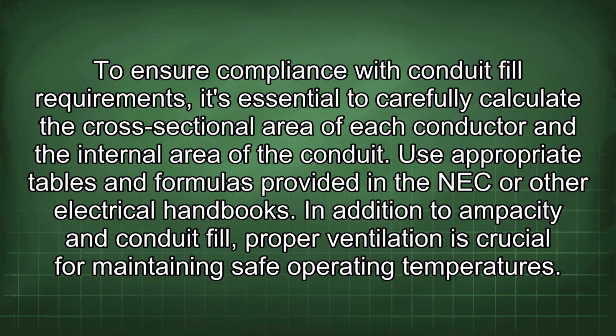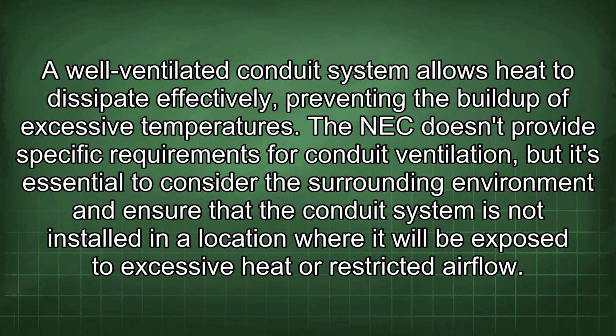In addition to ampacity and conduit fill, proper ventilation is crucial for maintaining safe operating temperatures. A well-ventilated conduit system allows heat to dissipate effectively, preventing the buildup of excessive temperatures. The NEC doesn't provide specific requirements for conduit ventilation, but it's essential to consider the surrounding environment and ensure that the conduit system is not installed in a location where it will be exposed to excessive heat or restricted airflow.